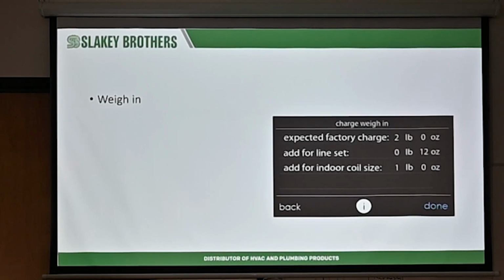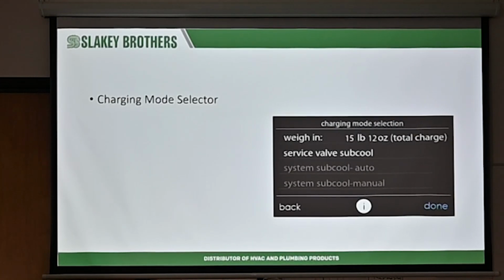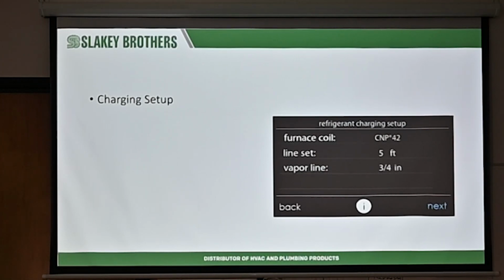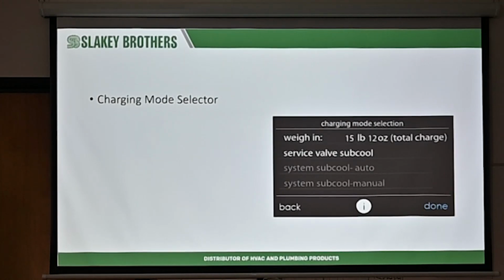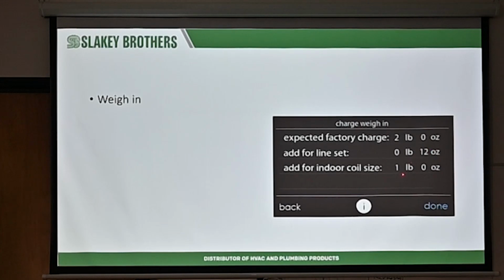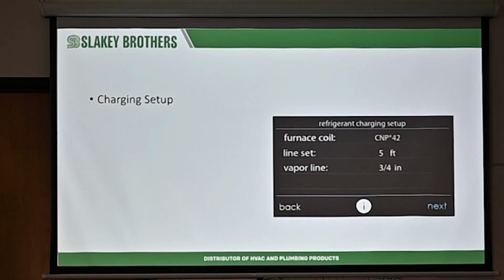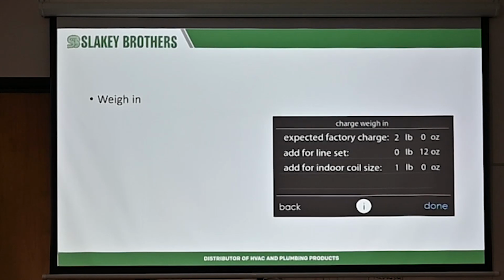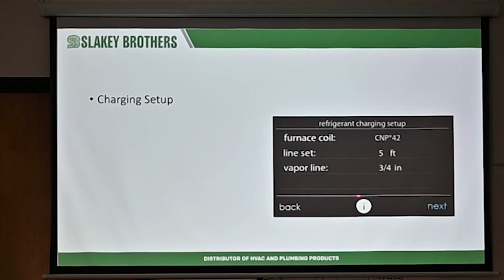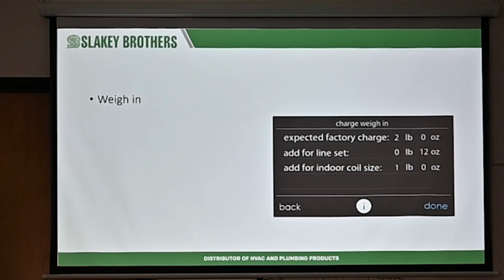So I never seen this line in a charge weighing. I mean, for indoor coil size, is it in? Only for variable speed. Yeah, I saw line set charging, factory charging, but never coil charging. That should be, well, this screen right here, they may have simplified it. Yeah, looks like they simplified it to say add this much refrigerant total overall, but in order for it to tell you this number, it needs to know the indoor coil and the line set size. It does the math and it tells you how much total refrigerant. Yeah, I think you're right.